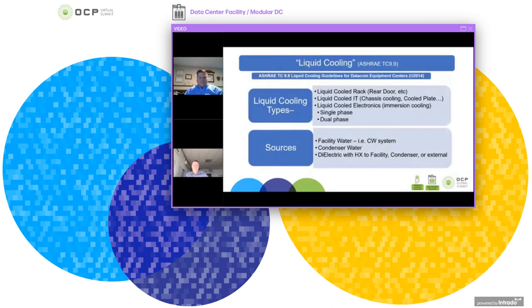So I started talking in terms of barbecues, because I think that's a term more people understand than kW of heat. Some people think liquid cooling is a new concept, but ASHRAE TC 9.9 has spent decades looking at liquid cooling. They've defined liquid cooling types, and to the extent that the Open Compute project wants to move forward, they should look at references from ASHRAE when talking about liquid cooling types: liquid cooled rear door rack, liquid cooled IT, liquid cooled electronics, and immersion, both single phase and two phase.